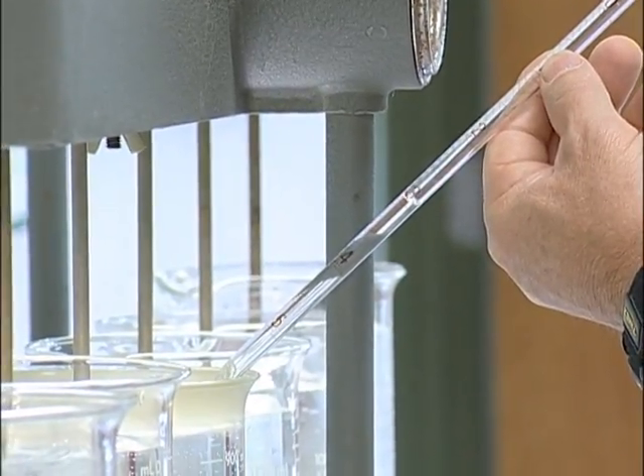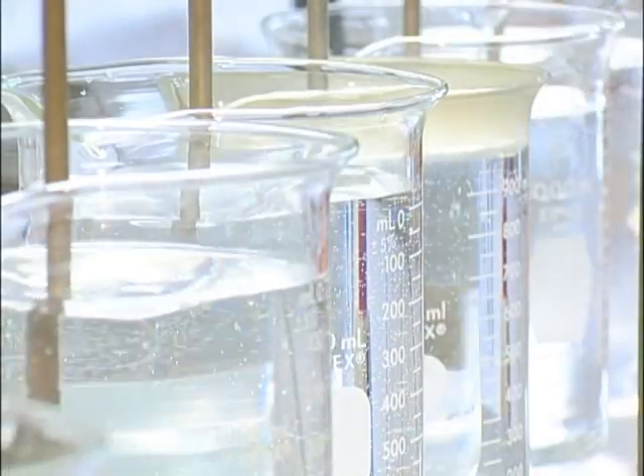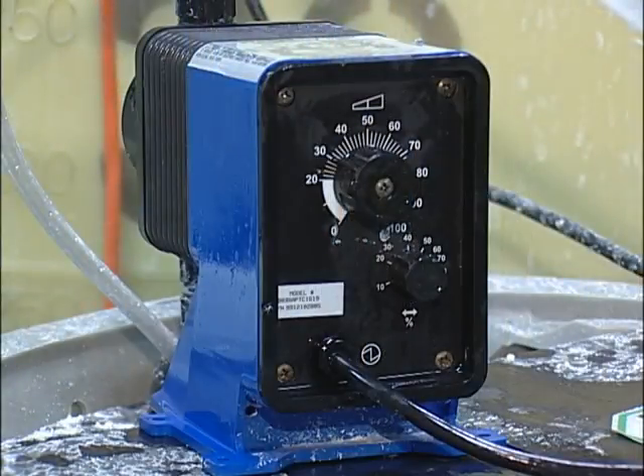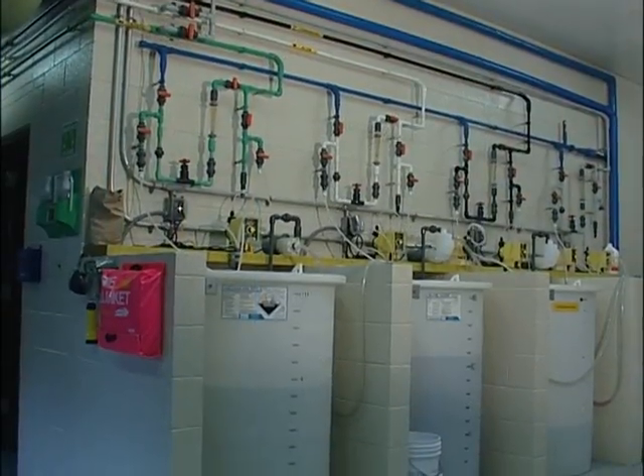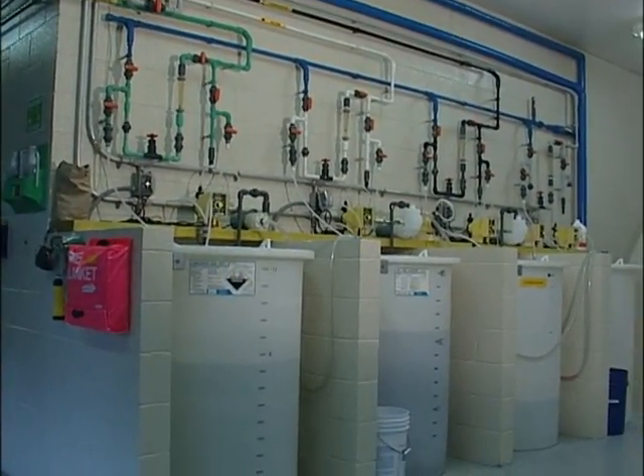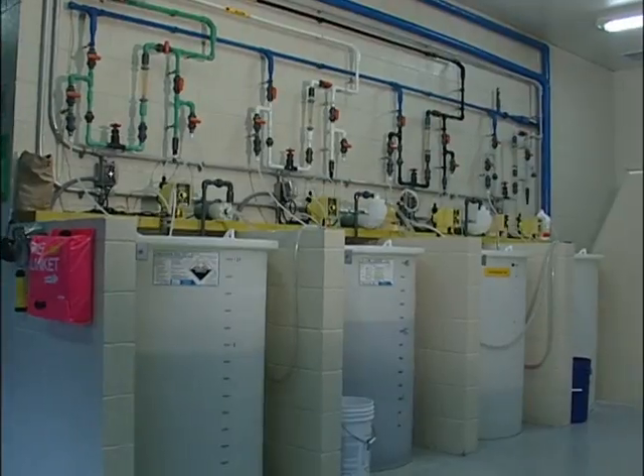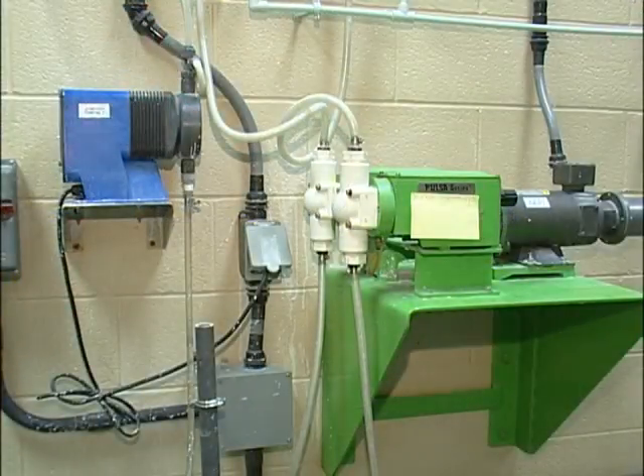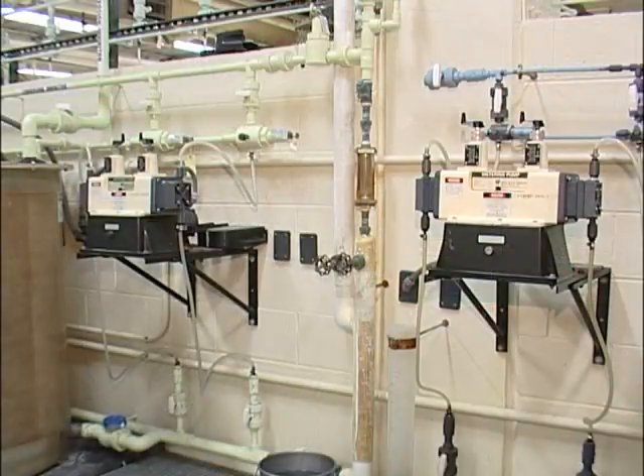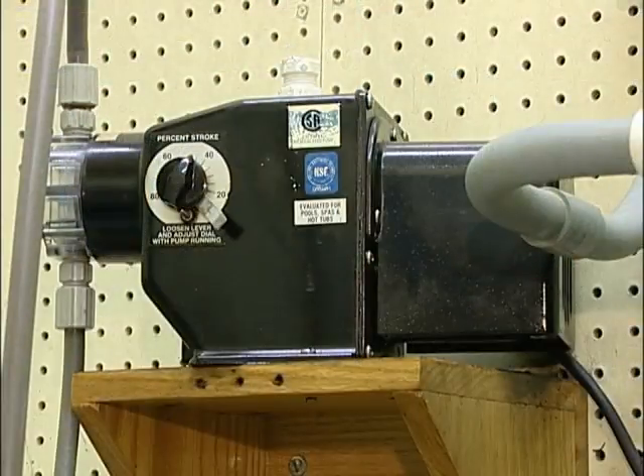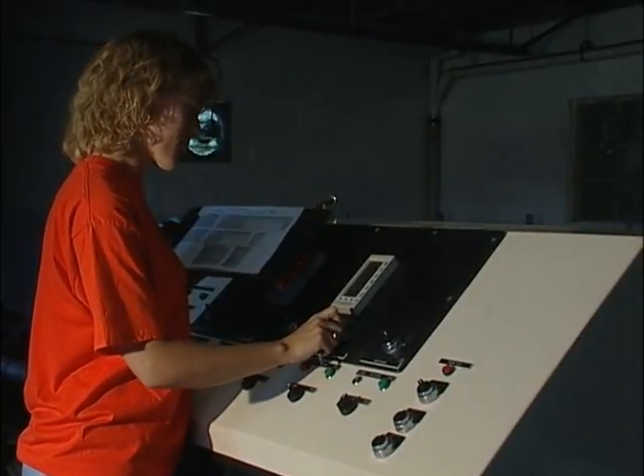Jar testing is often used to indicate the proper dose for treating your water. Once you have determined the proper dose, you will need some way of getting the chemical into the water. Usually, this requires some type of chemical feed pump. There are a variety of pumps and pump types to choose from. Choosing the right pump for the intended purpose is critical to the proper operation of the water treatment plant.